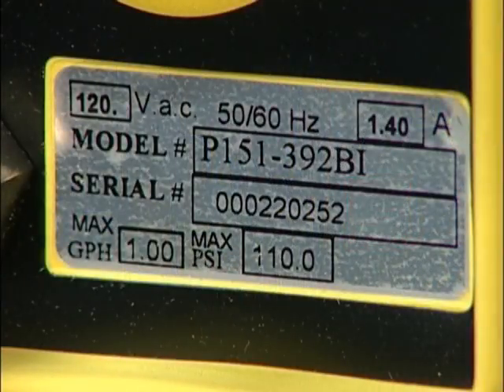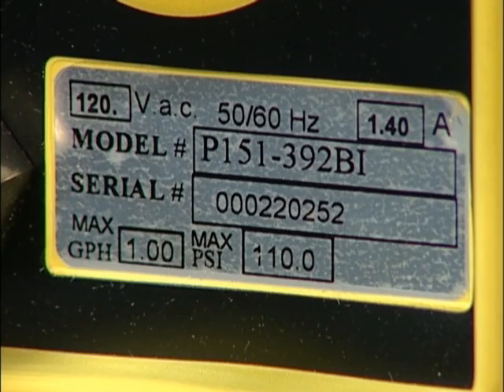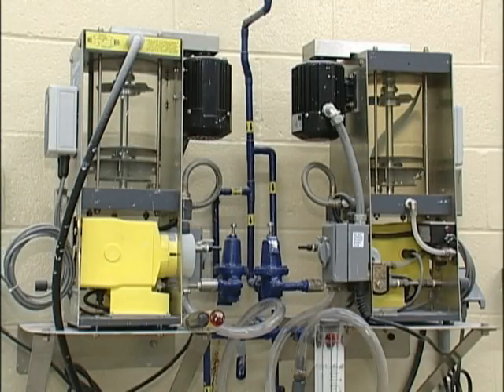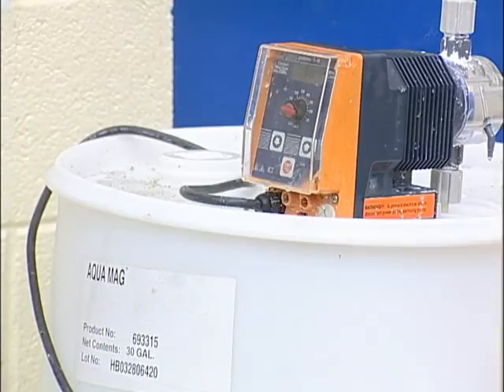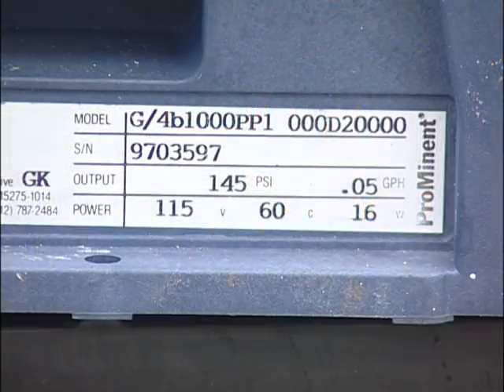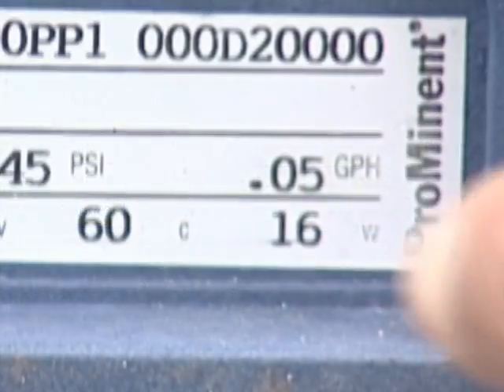Pump size in terms of capacity is a critical issue. There is no such thing as one size fits all when it comes to chemical feed pumps. Purchasing a pump that is not capable of delivering an adequate amount of chemical may seem foolish to some operators, but buying a pump that is too large may ultimately have the same effect: inadequately treated water. Some chemicals like polymers and polyphosphates may be delivered in very small dosages, so they often require pumps that can deliver small quantities accurately and consistently. The daily output of these pumps may be measured in fractions of gallons per day.